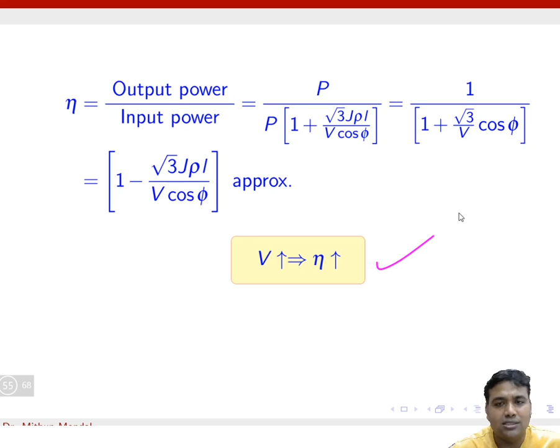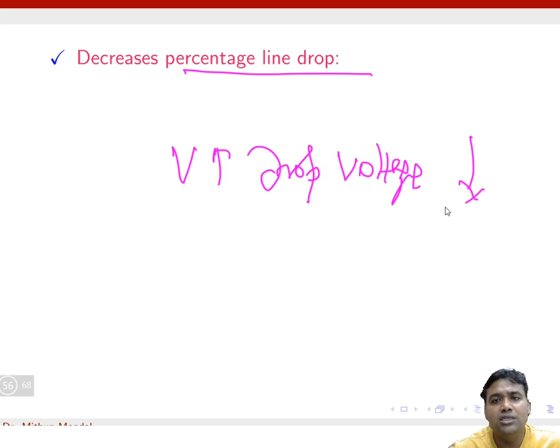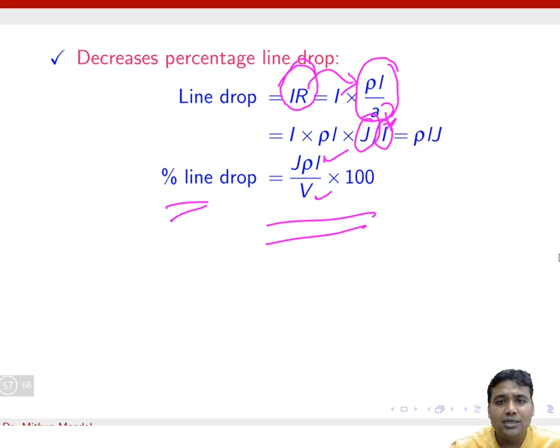The third advantage that we are getting is the decrease in percentage line drop. If you increase the voltage, the drop in the voltage reduces. How is it like that? Let us see. Percentage line drop: if you have a resistance of the conductor as R, then the line drop is IR. Then you substitute R is equal to rho L by A, and substitute the area of the conductor as I by the current density. Then you will get the line drop as this equation. J is the current density, rho is the resistivity, L is the length, I is the current, and V is the voltage. So the percentage line drop you have seen.